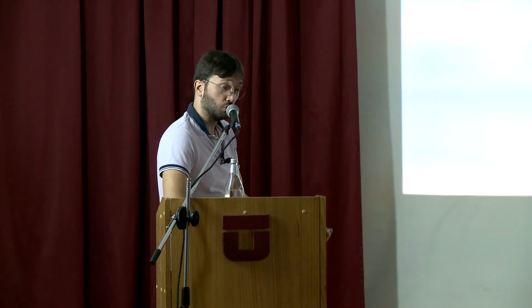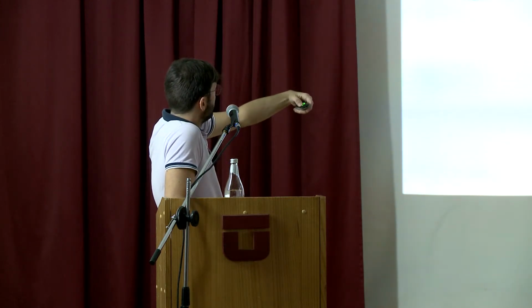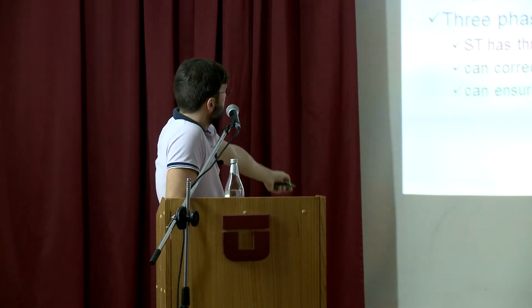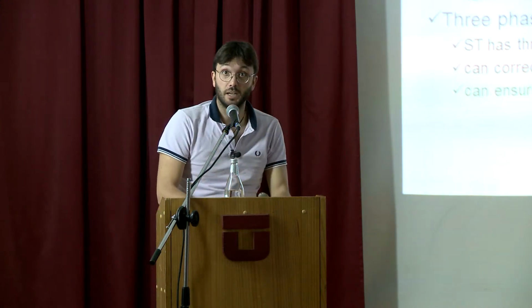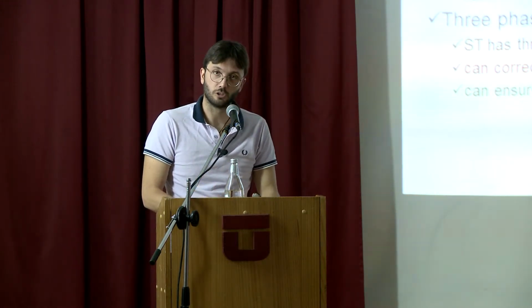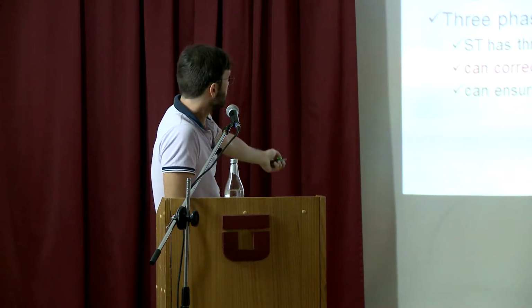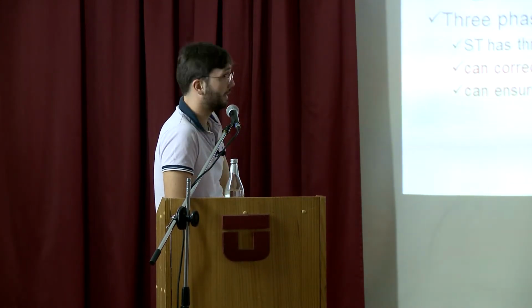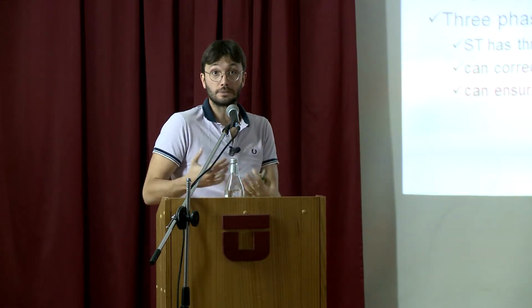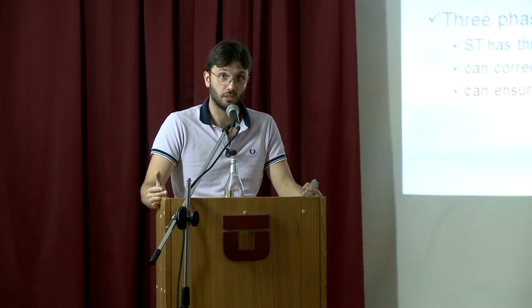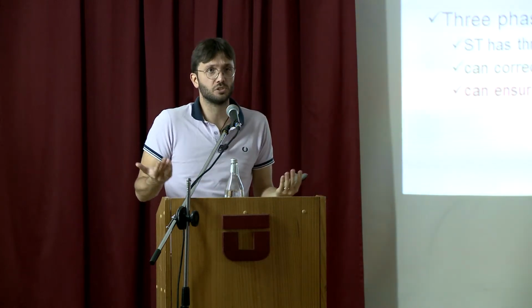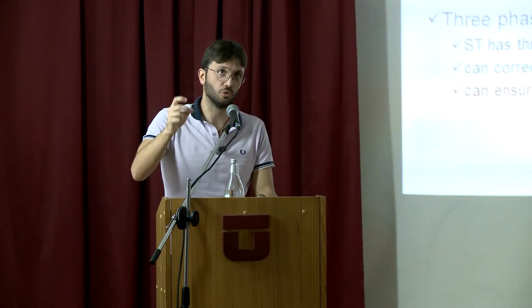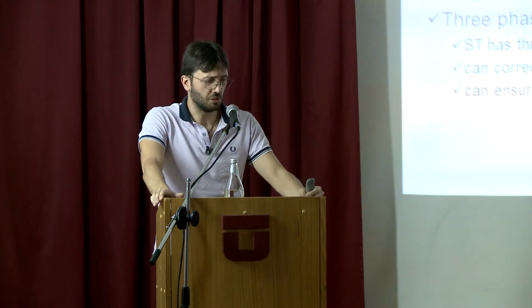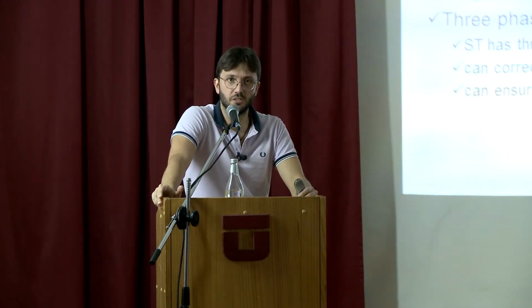Harmonic suppression: it is a fully controlled power electronics converter. I can compensate for the harmonics. I can always decide to get balance, meaning I can absorb balanced three-phase current, but maybe I can also try to correct the imbalance that is existing in the actual medium voltage grid. Meaning I can decide for the smart transformer, it doesn't make any difference. I can draw the power from the different lines, different phases independently.